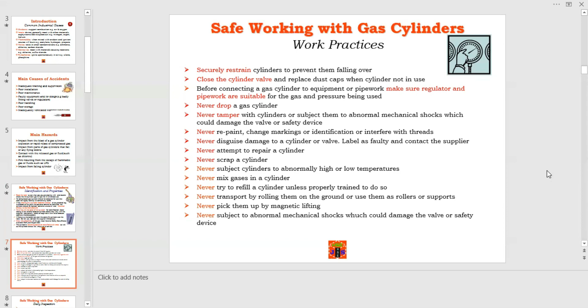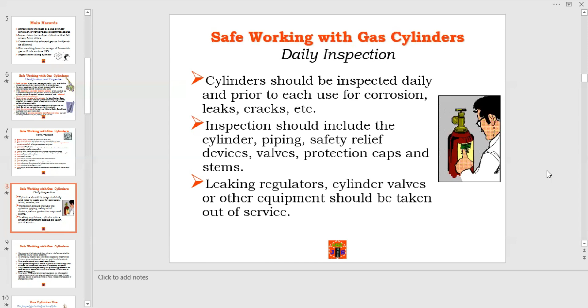Point number one, cylinders should be inspected daily and prior to each use for corrosion, leaks, cracks, etc. Point number two, inspection should include the cylinder, piping, safety relief devices, valves, protection caps, and stems. Point number three, leaking regulators, cylinder valves, or other equipment should be taken out of service immediately.